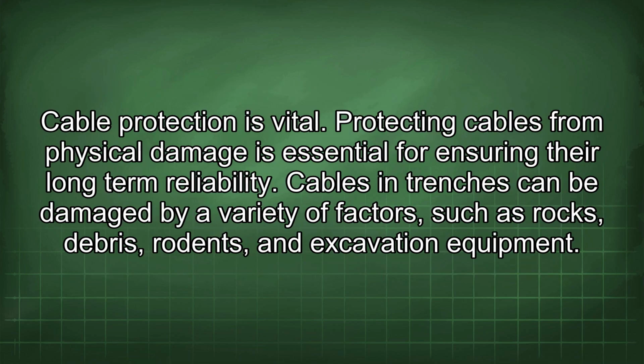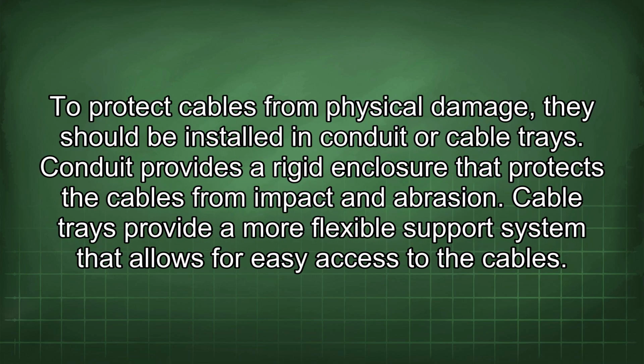Cable protection is vital. Protecting cables from physical damage is essential for ensuring their long-term reliability. Cables in trenches can be damaged by a variety of factors such as rocks, debris, rodents, and excavation equipment. To protect cables from physical damage, they should be installed in conduit or cable trays. Conduit provides a rigid enclosure that protects the cables from impact and abrasion. Cable trays provide a more flexible support system that allows for easy access to the cables.